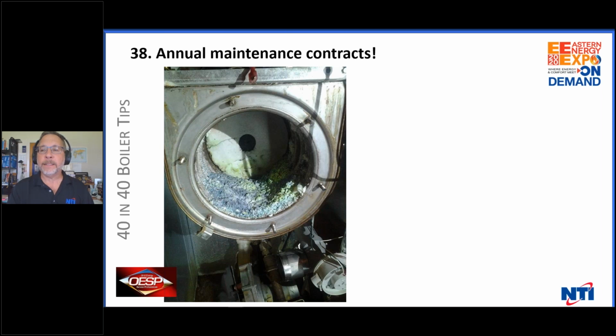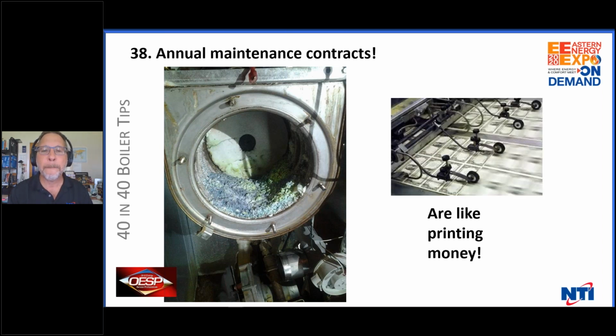Do annual maintenance. Sell maintenance contracts. This boiler, we were told, was defective. Can you believe that? Hadn't been serviced in only 11 years. Isn't that great? How many of you guys have gone out to an oil-fired boiler that hadn't been serviced for 6 years and it's taken you 4 or 5 hours to get through the soot with your soot saw and your vacuum to try to get the thing clean? Holy geez. Annual service contracts, maintenance contracts are like printing money.